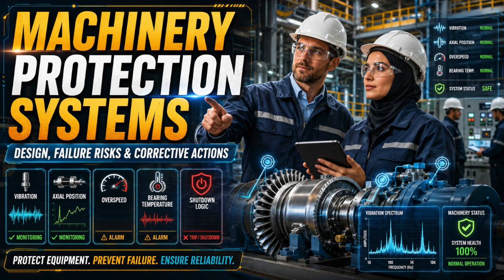It must have reliable power. It must support testing. It must capture peak speed. It must interface correctly with the shutdown chain. But here's the part many engineers miss. Electronic response time is not the whole overspeed response time. The total system includes sensor pulse generation, speed sensing surface geometry, signal processing, logic response, relay actuation, solenoid response, trip valve response, stored energy in the machine and process, and rotor acceleration rate.